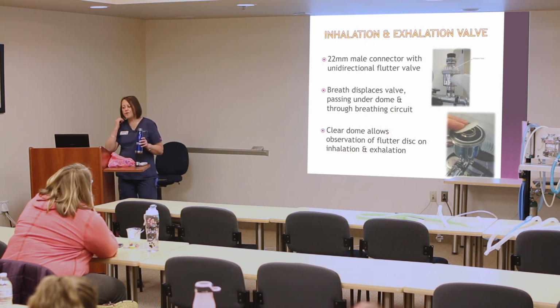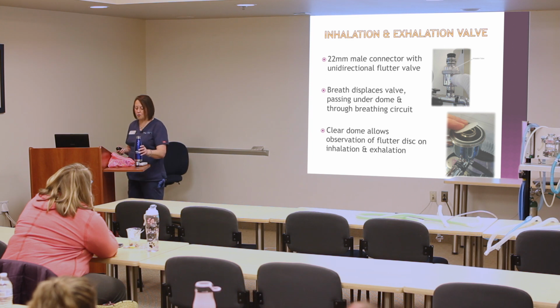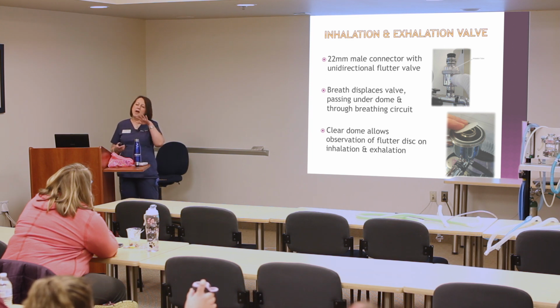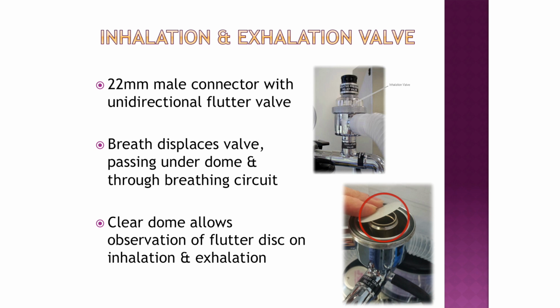So these one-way flutter discs are designed to prevent backward flow of gas through these machines, and they're nice because they do let you observe how the animal's breathing. Usually they're going to be alternating. One disc will be going up while the other disc is going down, and they do have to sit flat over those holes here. And every now and then we have a flutter disc that gets warped, and it will also let carbon dioxide carry around in this circle. And we actually had that happen not too long ago with that new blue machine that we got.